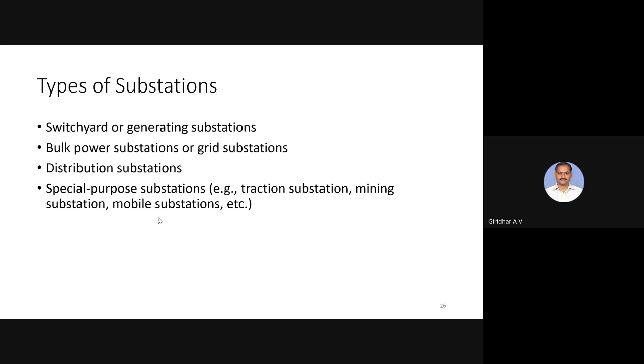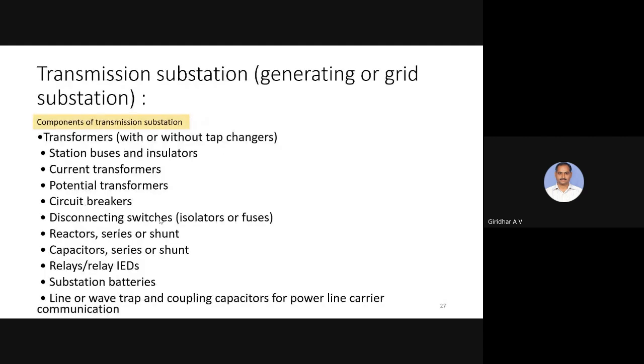If you analyze from the lower layer onwards, we have various field devices from the substation, and we are trying to get data from these field devices: switches, isolators, CTs, PTs, for voltage, current, power. All the measurements should be monitored, and appropriate control actions will be taken. We have various substations, generating substations, bulk power substations or grid substations, distribution substations.